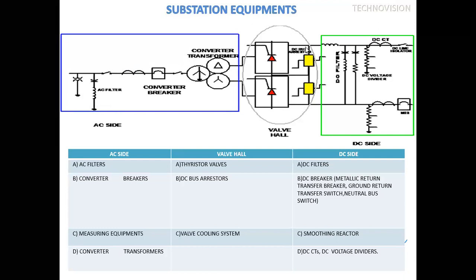Then here we have the smoothing reactor at the DC side. If you take the DC side, there are smoothing reactor, then surge arresters are there, DC filters. Later on DVD. DVD means DC voltage divider. See, the principle of DC and AC quantity measurement is very different. When I want to measure AC quantities, it's a transformer action, that is, we can say induction effect. But take the case of DC, measurement is not so easy. So for the measurement of DC voltage, we use the DC voltage divider, DVD.